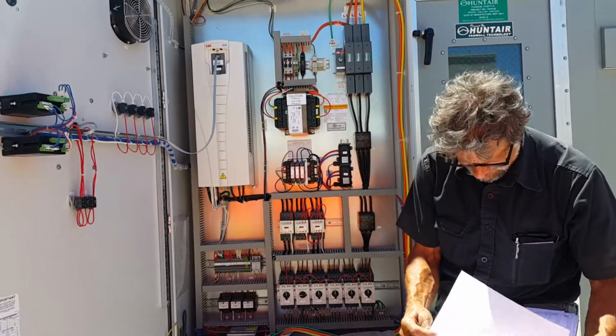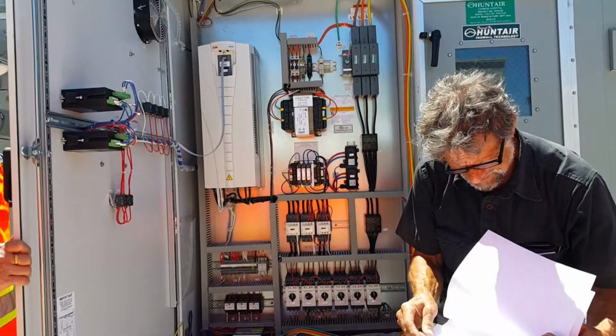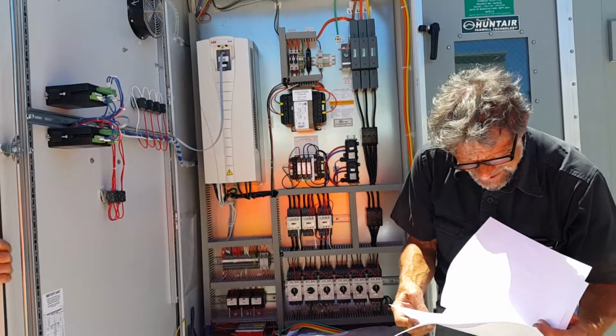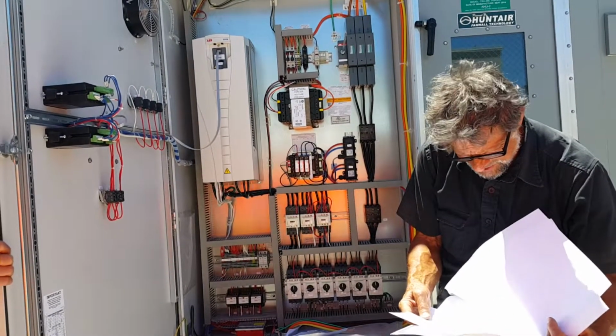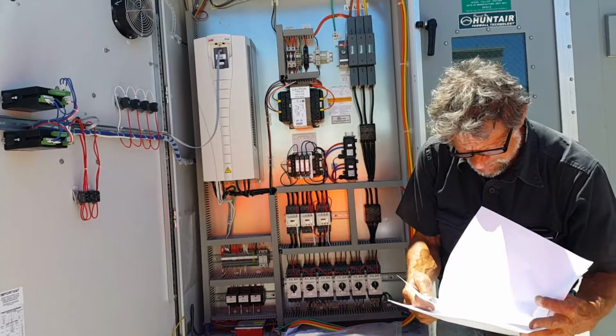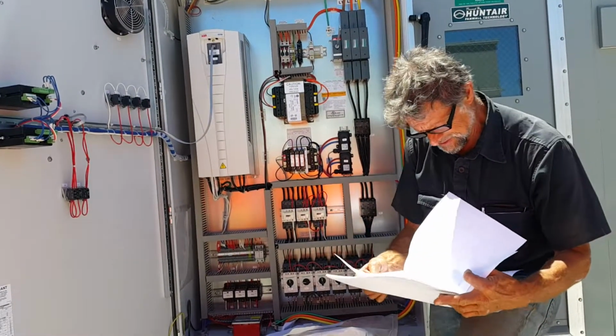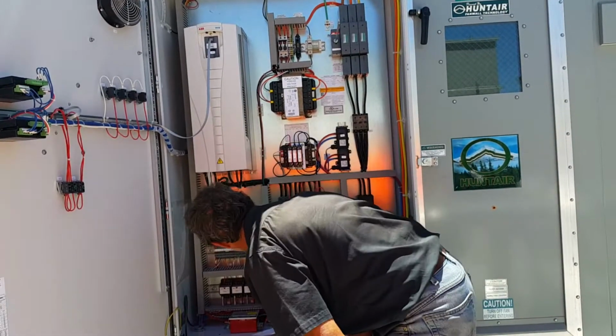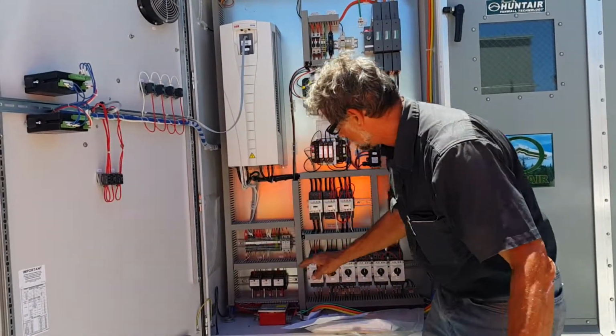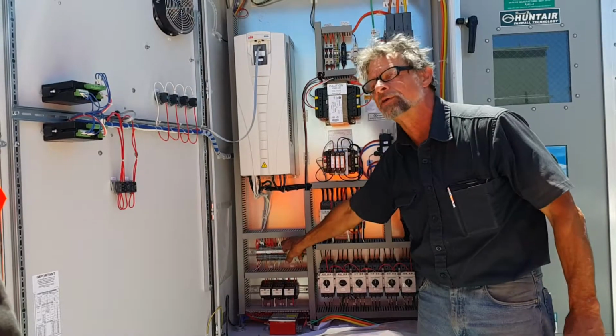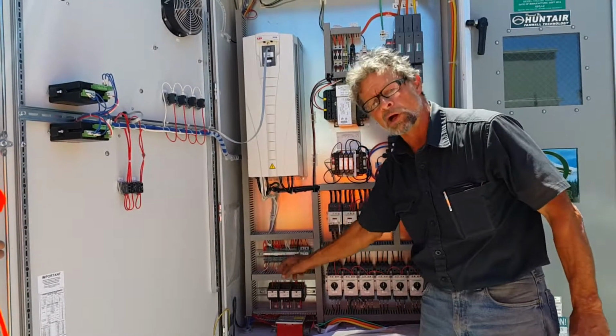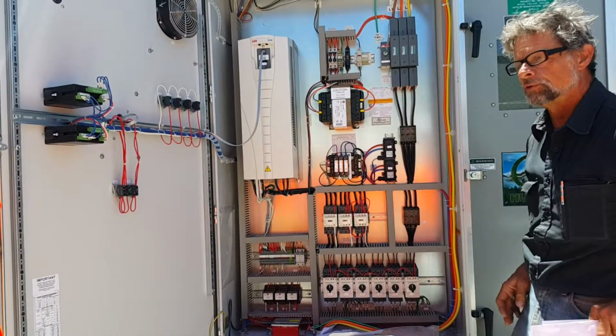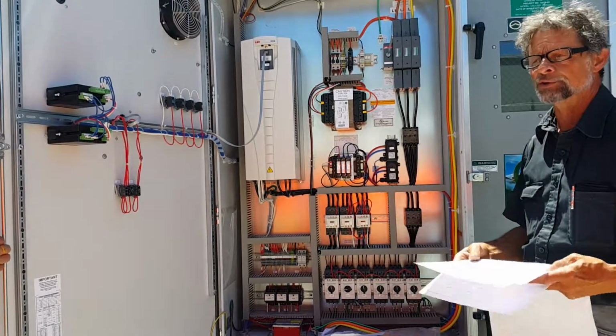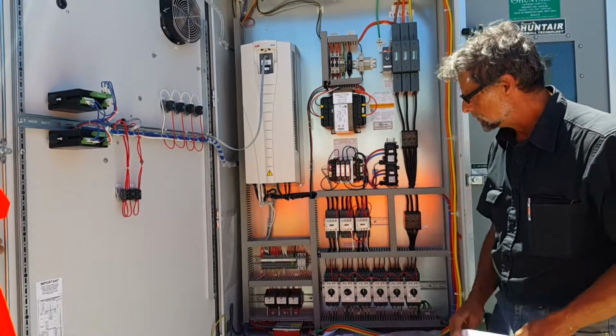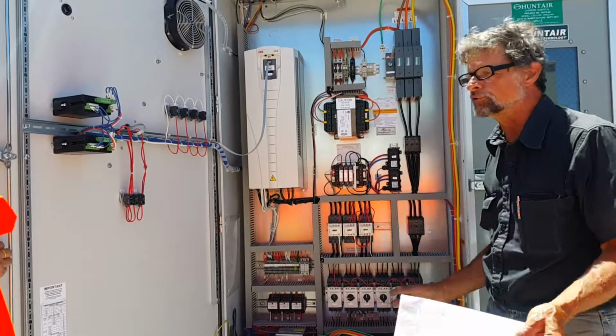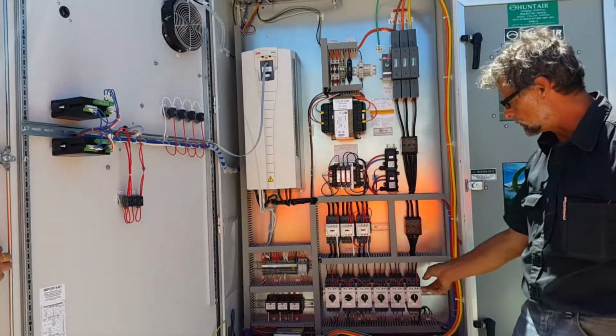Let's see what we got on this one. TB1 151, P6. Yeah, 151 and 152. In this case, they just ran them to a set of contacts here. So you can put a set of wires on there and tell whether it's open or closed. They opted not to do it. Closed contactor, but you could pick it up there and it would give you a signal somewhere, whatever you want to do with that signal.